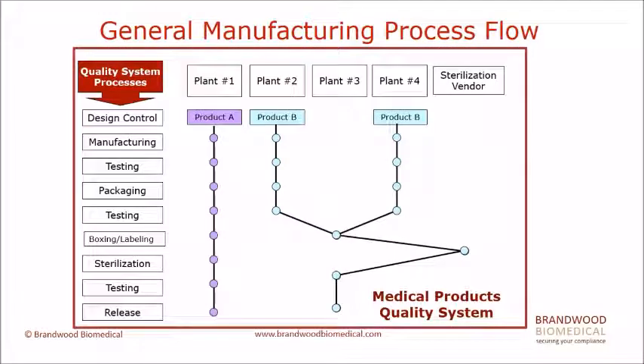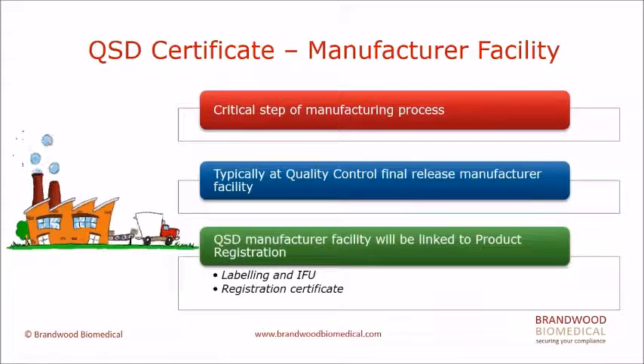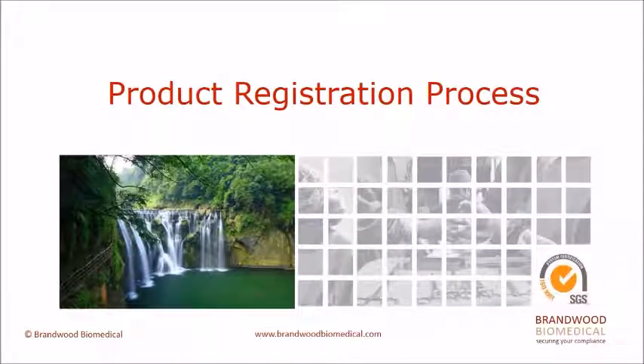For product B, a single product is manufactured in multiple facilities. So in this case, how do you determine the manufacturing facility for QSD certificate? So there are some key factors. QSD certificate, the manufacturing facility, normally at the critical step of the manufacturing process, and it's typically at the quality control, final release manufacture facility. The QSD manufacture facility will be linked to the product registrations. So the manufacture facility will show on the labeling and instruction for use, as well as the registration certificate after approval. So once the QSD is approved, we can start prepare for the product registrations.